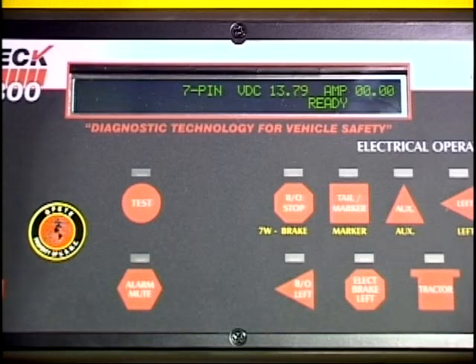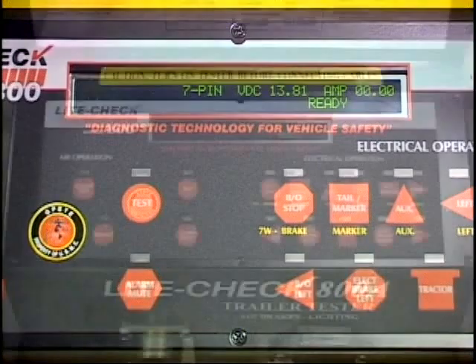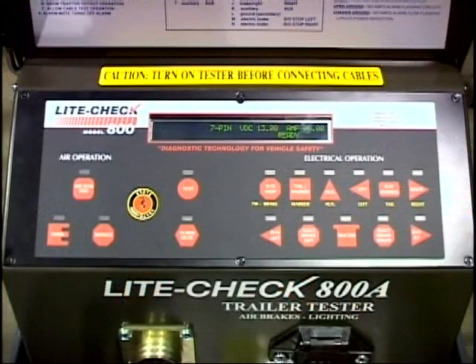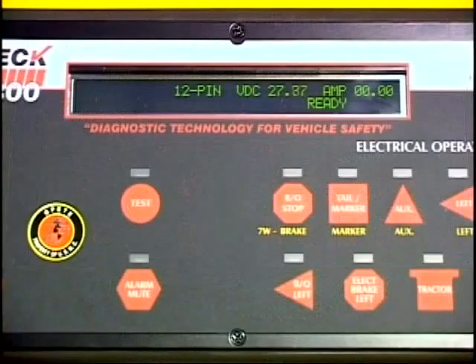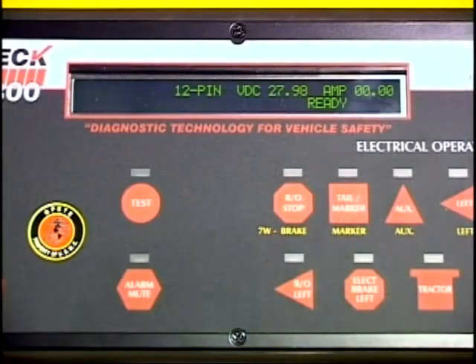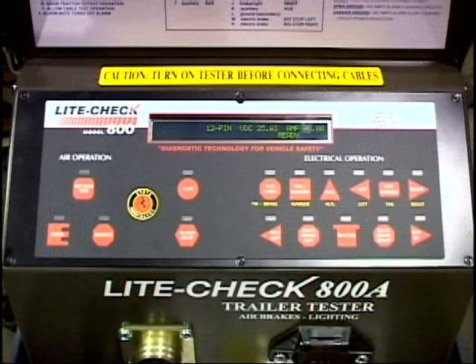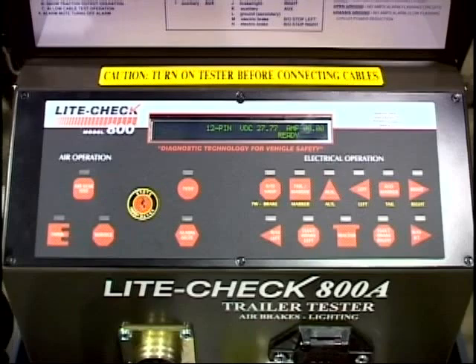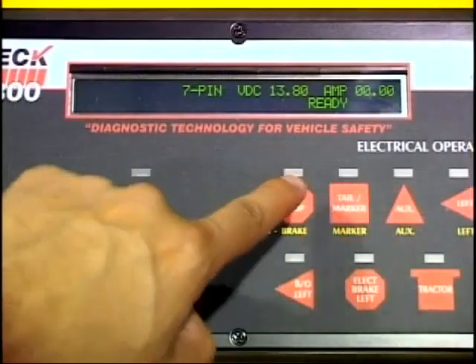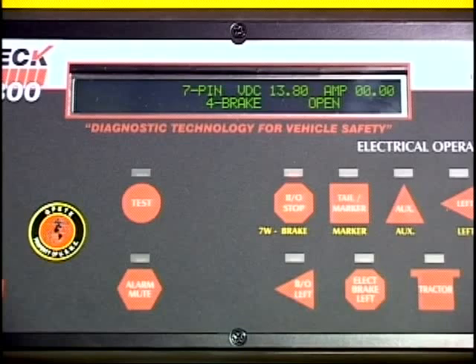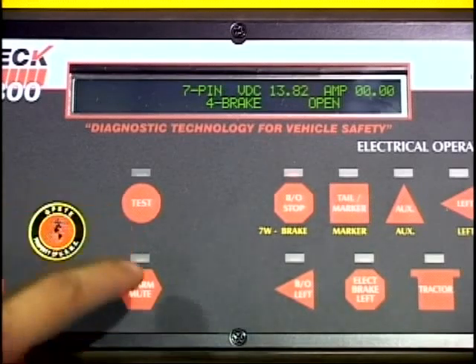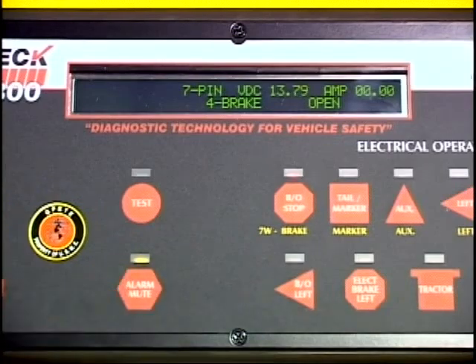The display will show a ready message indicating the tester is ready for trailer 12-volt 7-pin operation. Only the top 6 lighting keys will be used for the 12-volt mode. The display will show a ready message indicating the tester is ready for trailer 24-volt 12-pin operation. There are 10 lighting keys, labeled black out, to be used for the 24-volt mode. The tester will automatically identify opens, shorts, open grounds, and chassis grounds, and sound an alarm. With the alarm, the mechanic can work on the circuit and the alarm will quit when the fault is corrected.